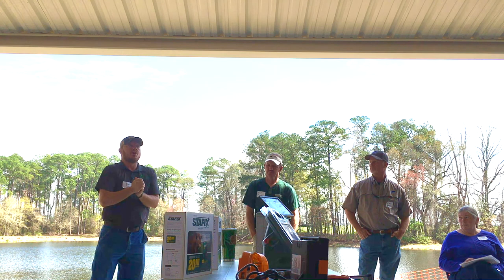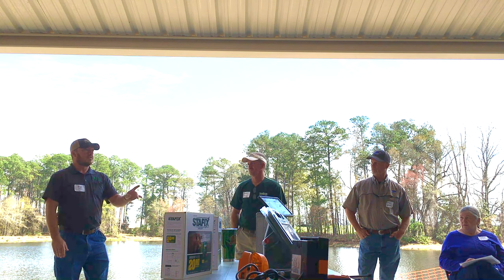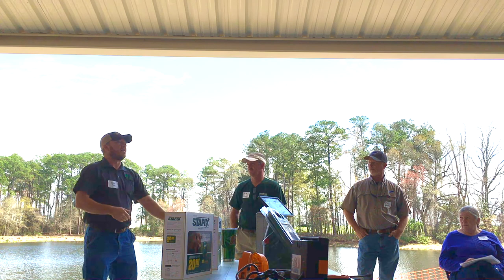I've had guys say, well, I got a lightning arrestor out there. How many ground rods you got on it? I got one, I got a ground rod up to it. Okay, one ground rod. How many ground rods you got on your charger? Well, it's got 3 or 4 or 5, whatever. I said, so you've got a stronger ground field over here than you do on your lightning protection.